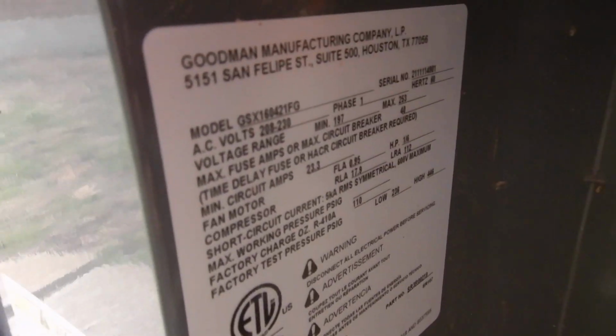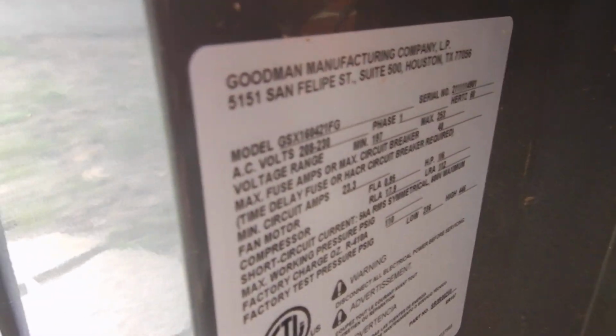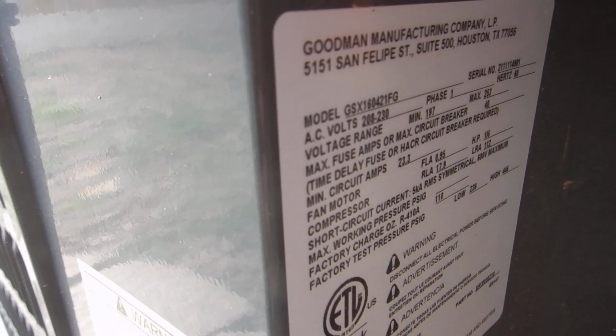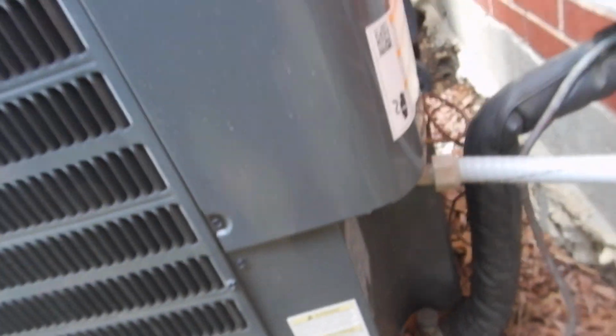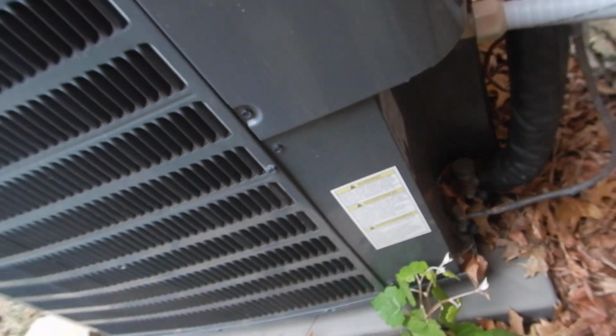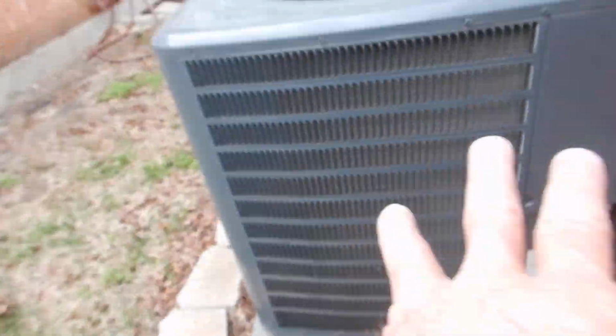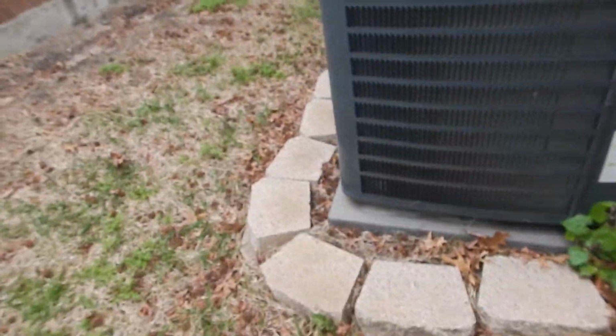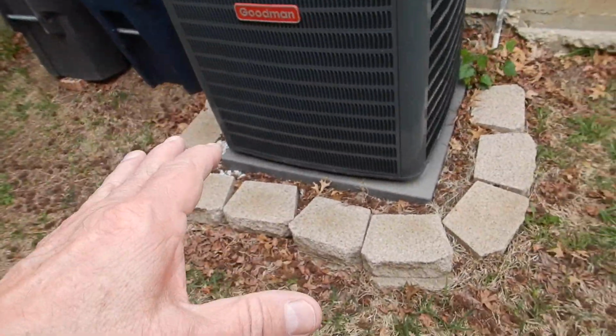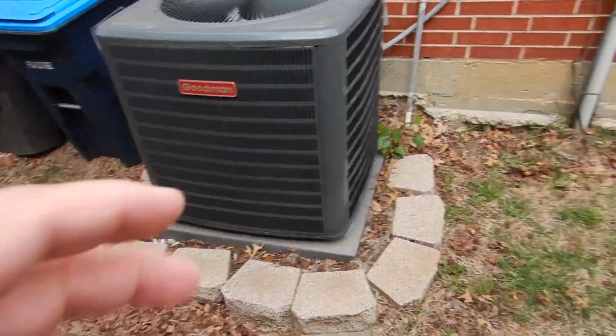This is our data plate right here that tells you a lot of what we've been talking about. So we got dirty coils. We do not have the right type of Schrader valve caps. Our condensing unit is not level. Is that all you got, bud? Almost. It's properly fused, by the way. It's a 4-ton system, 3 years old.